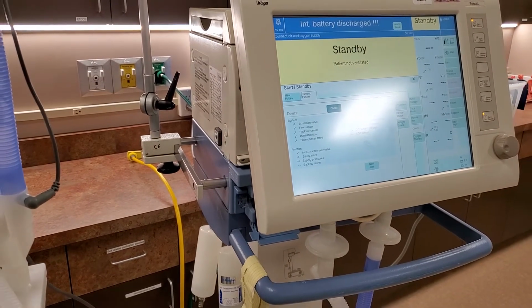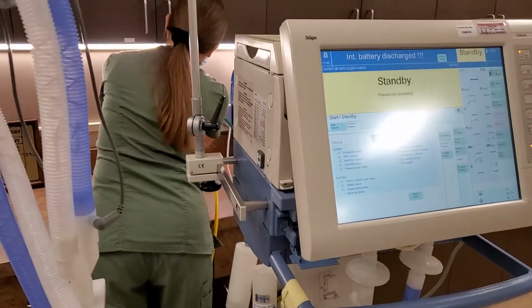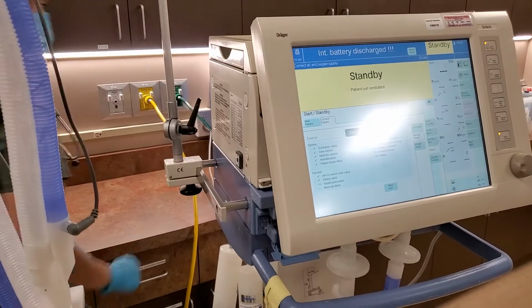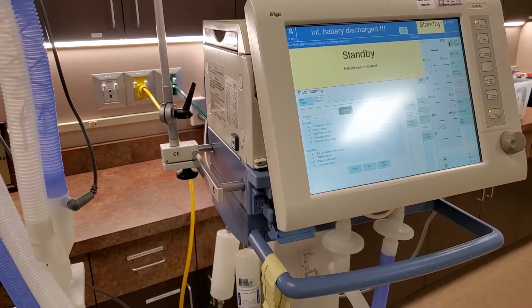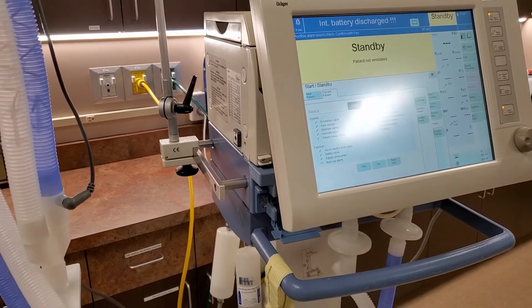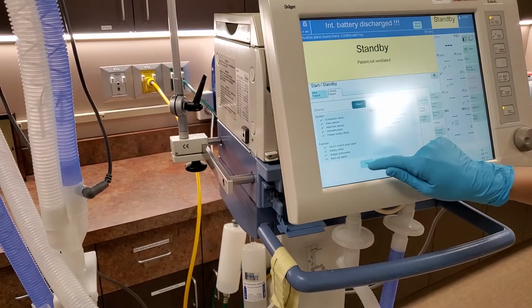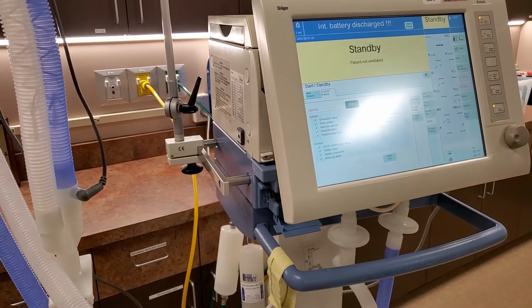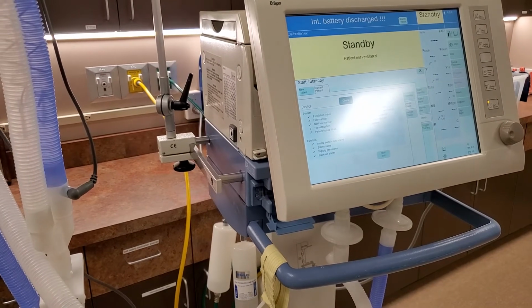Disconnect air and oxygen this time. Now it's saying audible alarm sound check. You have to confirm with yes. It's going to keep beeping until you do that. It says the calibration is okay.